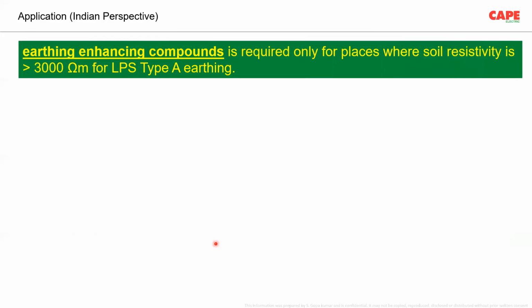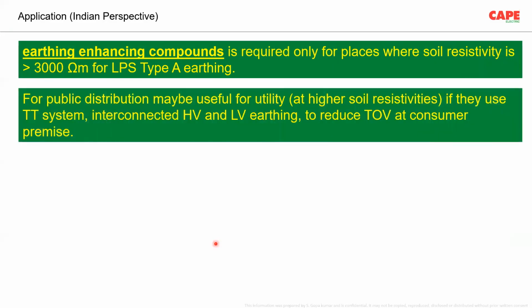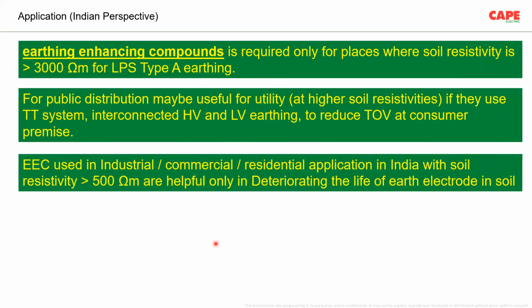But now to our situation, earth enhancing compound is required only for places where the soil resistivity is higher than 3000 ohm meter for LPS type A earthing. For public distribution, this may be useful for the utility company if they go for a TT system, interconnected system. Number 3, earth enhancing compounds used in industrial, commercial, and residential applications in India, where the soil resistivity is higher than 500 ohm meter, are helpful only in deteriorating the life of the earth electrode in soil.